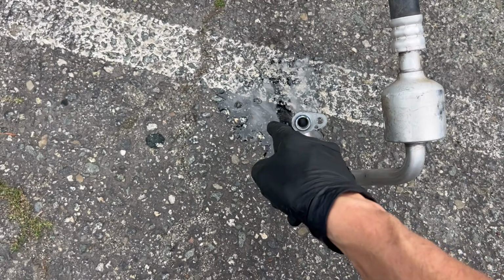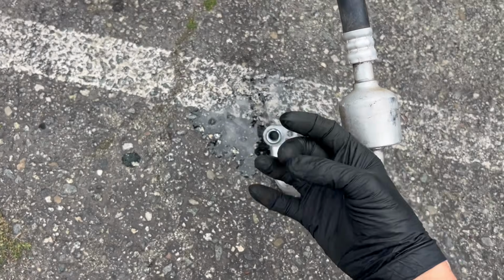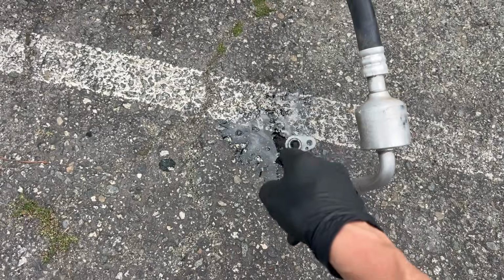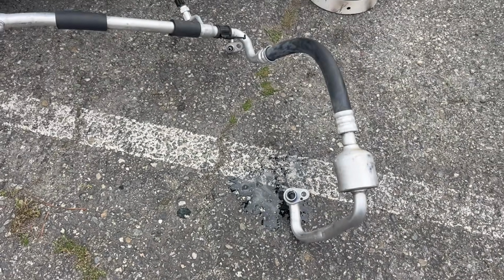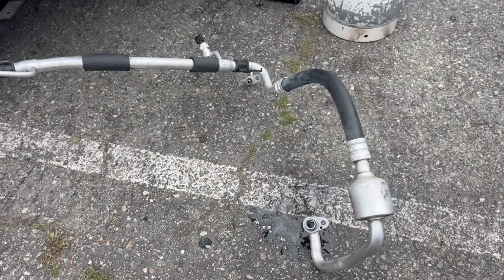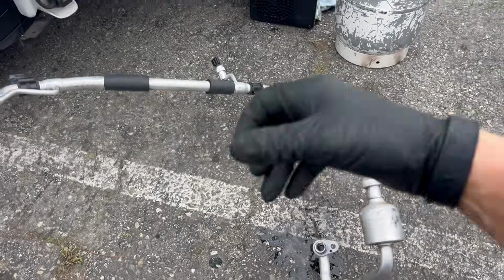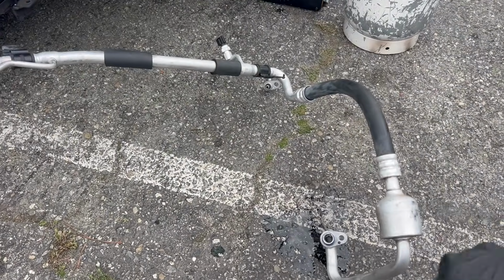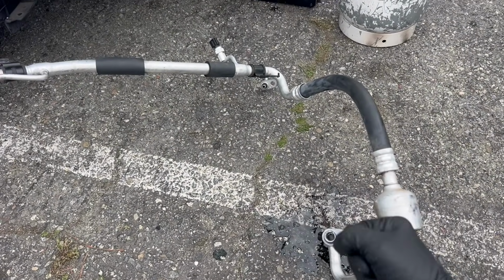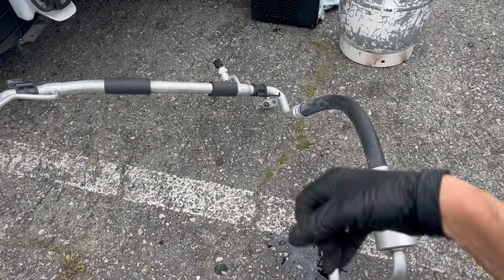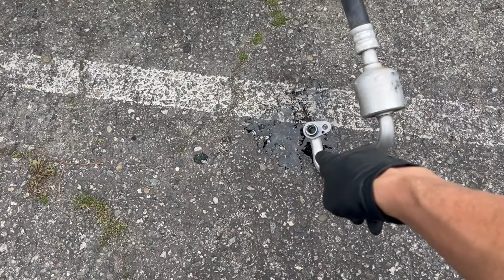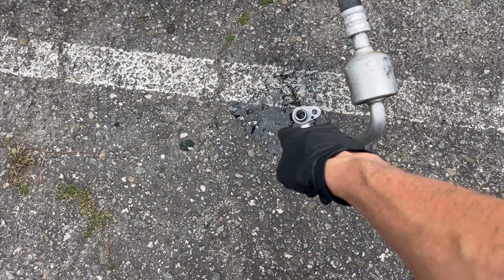That is refrigerant trapped in the oil, just like CO2 is trapped in the Coca-Cola. You got a Coca-Cola, you take off the cap, you hear that pop, you hear the fizzing come up, right? You take a few drinks, put a cap back on it, take it out of the refrigerator later on, and all of a sudden it bubbles up again. If you shake it, it bubbles up again. The refrigerant was trapped in that oil.